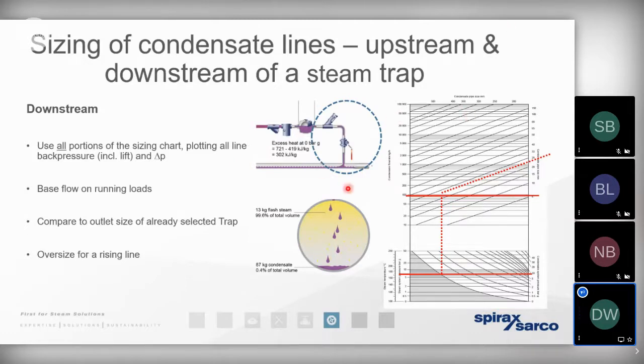So here you can see good working practice with regards to how we size a condensate pipework to allow for that biphase, that rapid expansion. So at the bottom part of the graph, we've got the pressure drop, 7 bar gauge running across to atmospheric. On the top part, we've got the mass flow rate, 100 kilograms per hour. So we take the dotted line and we run the line up diagonally.